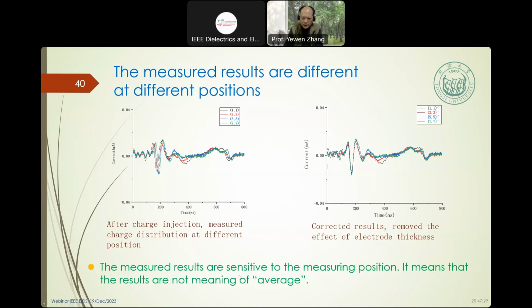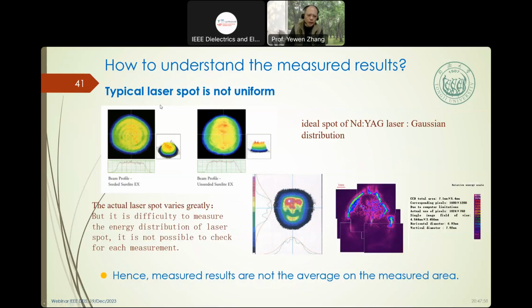So the measuring result is sensitive to the measuring position. It means the result is not a uniform average. Consider the laser: the typical laser spot is not uniform. This one is not our laser, it is typical from the manufacturer. Even this laser is not uniform, something like this. Our laser is closer to the ideal spot, a Gaussian distribution, so our laser is less non-uniform. Hence the measurement result is not a uniform average, and not a measurement error.